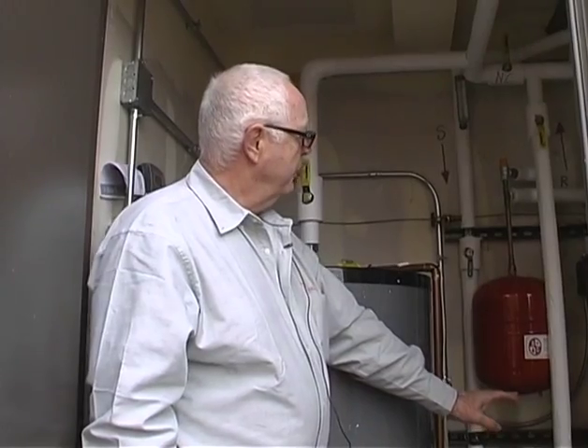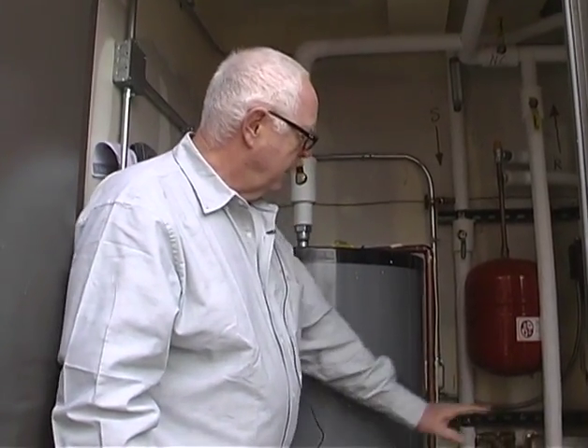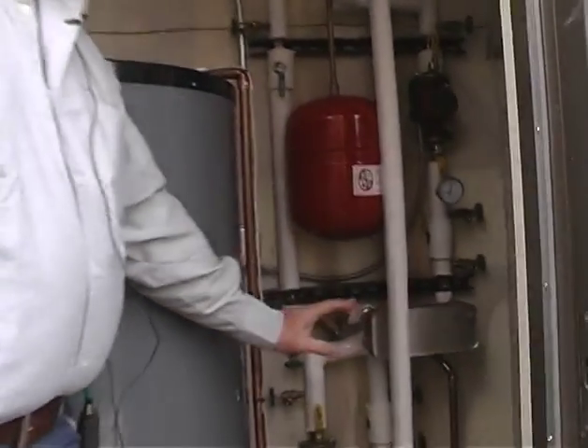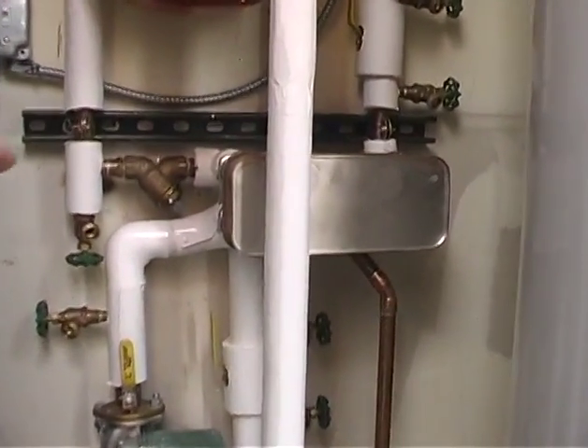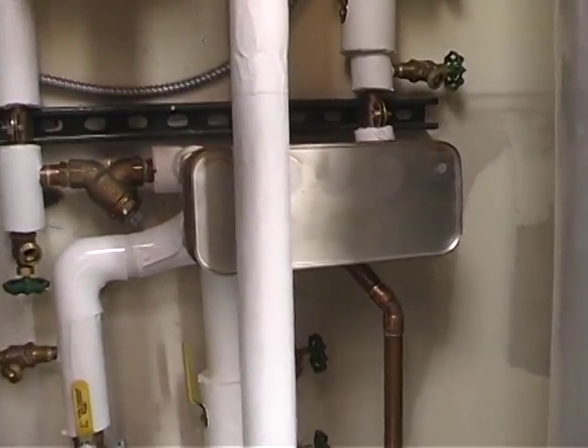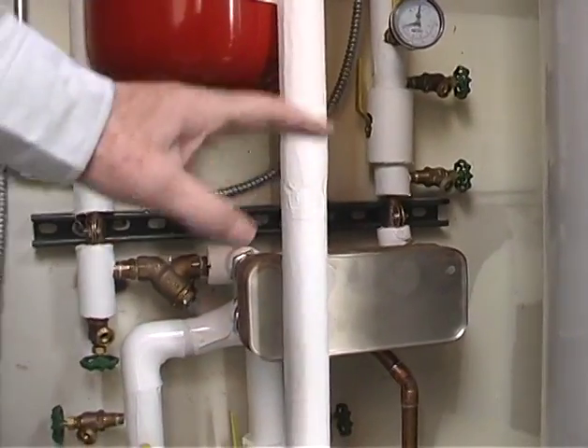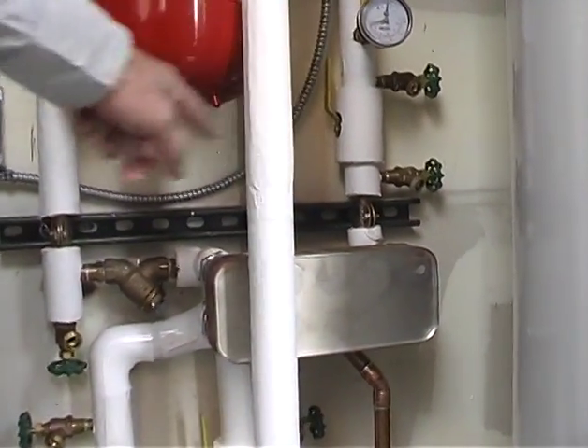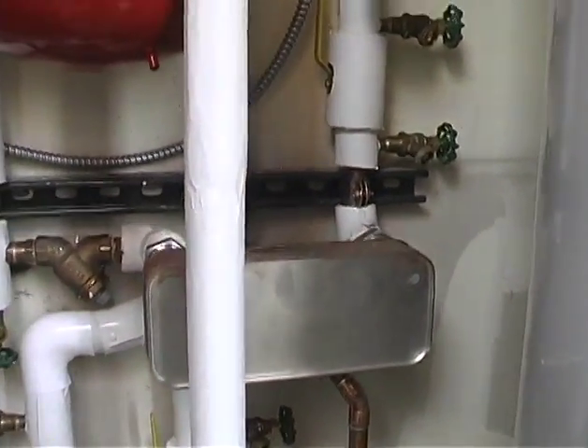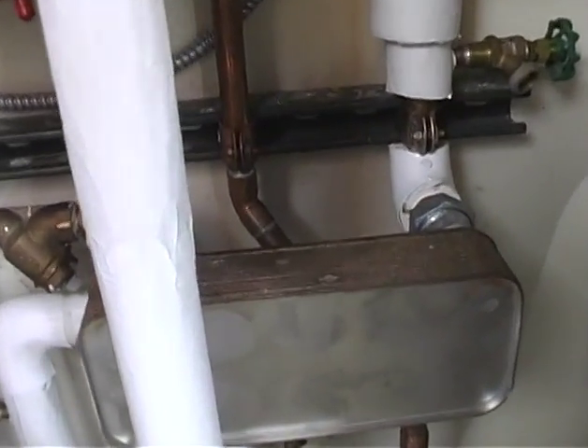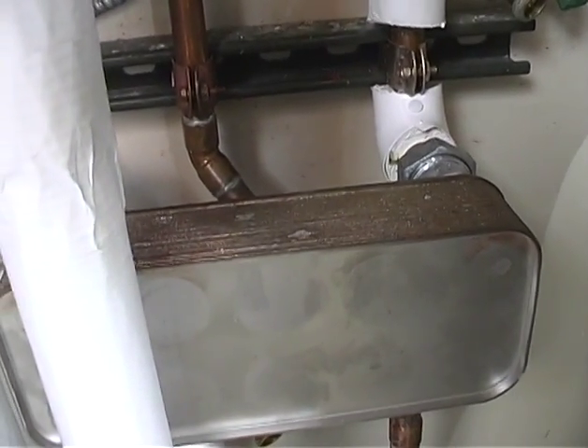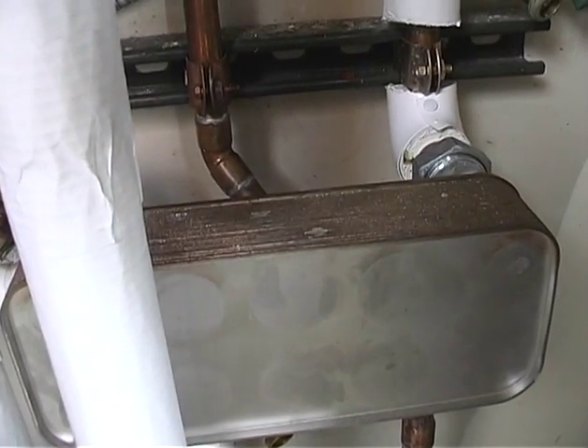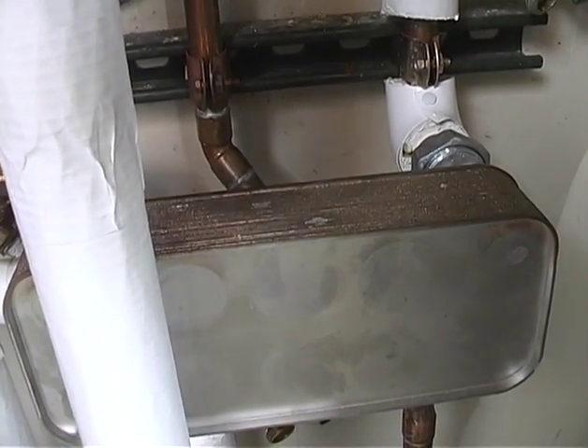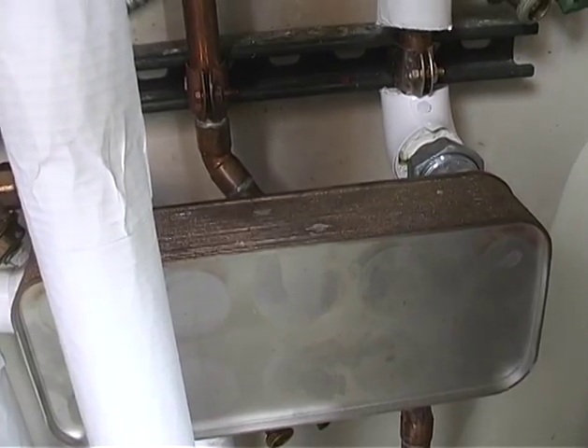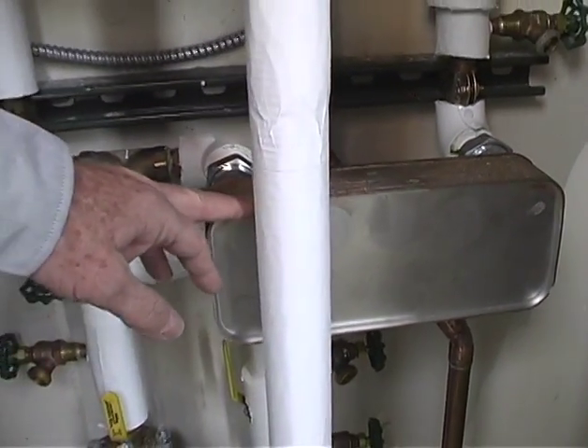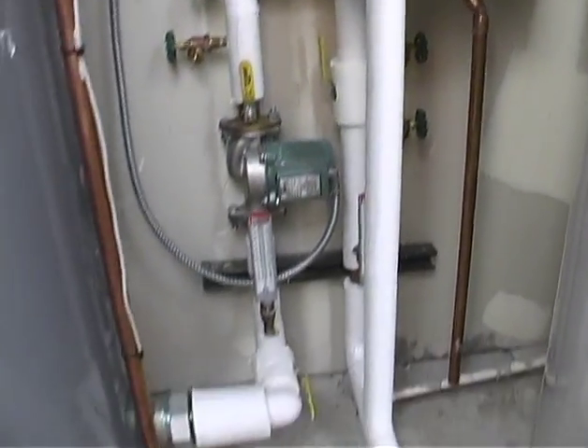Once this comes down here, the heat exchanger is now dealing also with the water. It takes the heat from the glycol and transfers it through these panels, which are kind of like book panels, pages put together. Hot water goes through it, glycol goes through it. They don't touch each other, but they exchange the heat. And the heat comes from here, from this heat exchanger, into this tank.